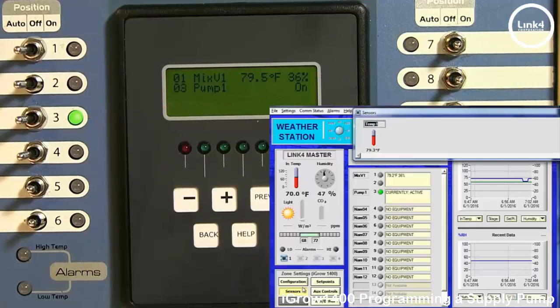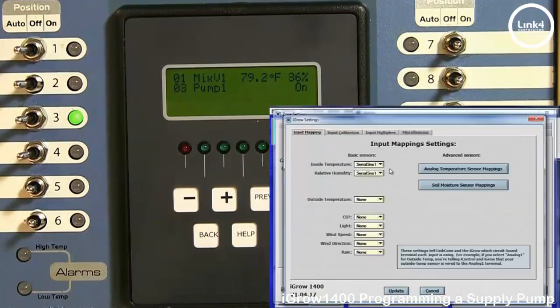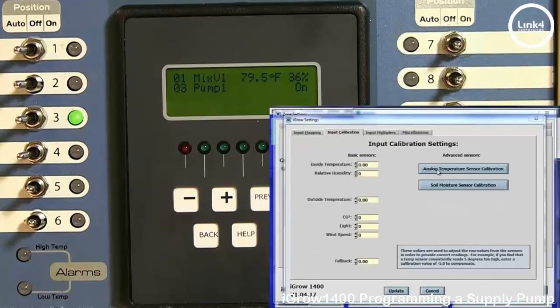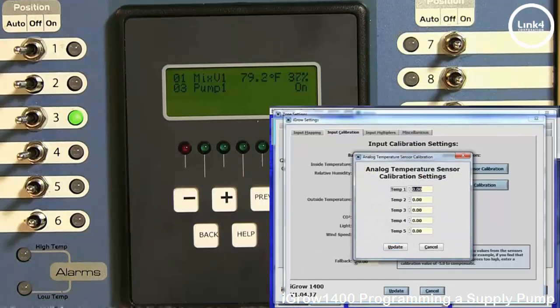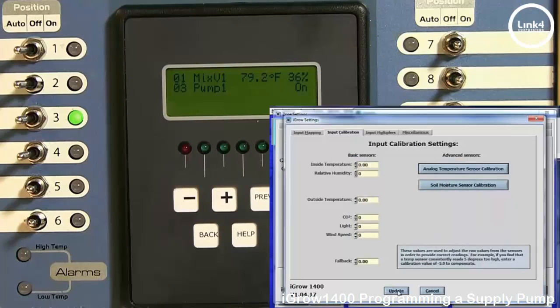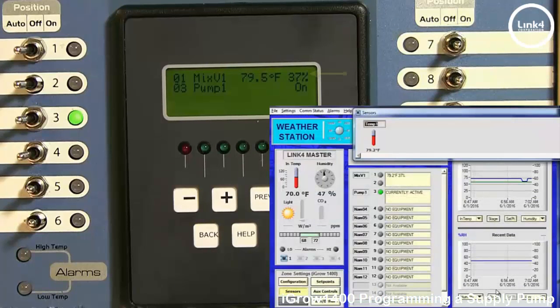Now to force the pump off, we'll simply go back into our configuration, and we'll go ahead and go into our analog temperature sensor calibration and just go ahead and simply change it. And by changing it, the mix valve is closing, and once it gets below the threshold of 5%, the pump will in fact turn off. And that's our video in programming a pump on the iGrow 1400 controller.